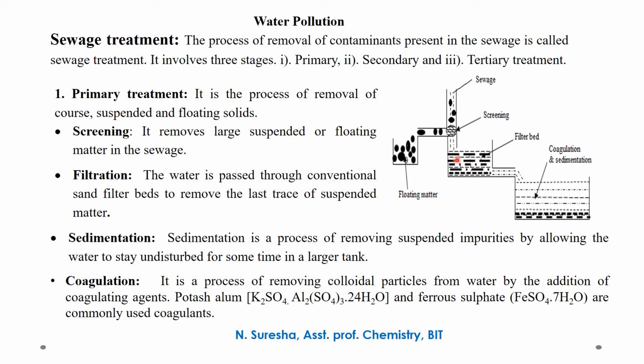When it is passed through the tank containing a sand filter bed, the suspended impurities can be removed and then it will be taken into large sedimentation tanks for coagulation and sedimentation. Sedimentation is the process of removing suspended impurities by allowing the water to stay undisturbed for some time in a larger tank. The suspended impurities present in the water will collect at the bottom of the tank.